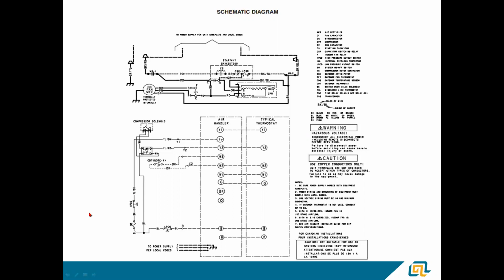So that can be a little bit hazy to troubleshoot. You might find that you have 24 volts on either side of your contactor, but no voltage across it because of that open common if your low pressure control is open. There's a little rectifier right here. The solenoid in the compressor for these units is a DC voltage solenoid. So they have this little diode stack or rectifier to change the 24 volts AC coming from the furnace into DC power to feed that solenoid.